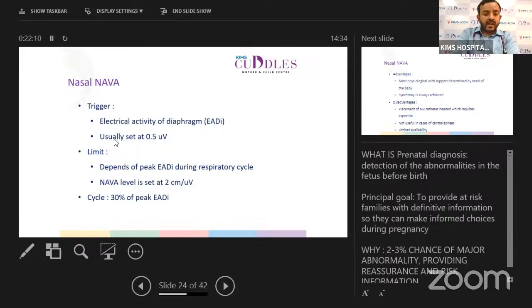The electrical activity of the diaphragm, the trigger is usually set at 0.5 microvolts. The limit in nasal NAVA is kept at, it depends upon the peak EADI during the respiratory cycle, and the NAVA level is usually set at 2 centimeters per microvolt. That is, for each microvolt of electrical activity that is generated by the diaphragm, 2 centimeters increase of PIP is seen, and cycling is done at 30% of peak EADI.